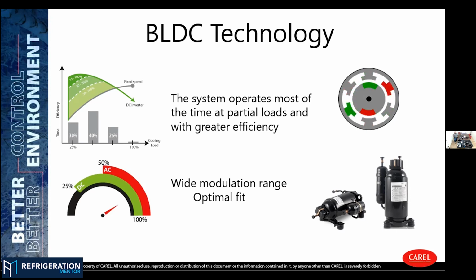You can see that at 100%, when the application needs 100% of the cooling capacity, fixed speed motors are more efficient because you don't have the inverter, you don't have any component in the middle between the electrical power and the motor. But when you need some modulation, variable speed compressors are more efficient than the fixed speed ones, as we can see here. And luckily for the people who promote the BLDC technology, the cooling loads most of the time are in partial load conditions.